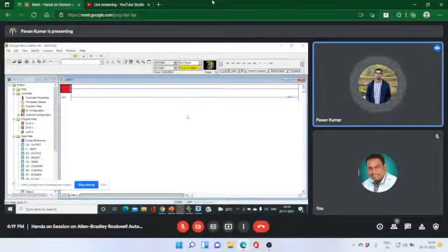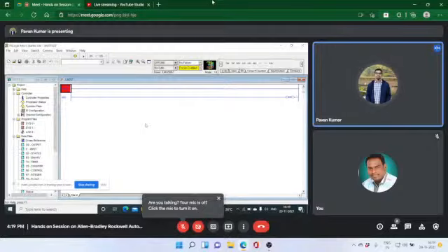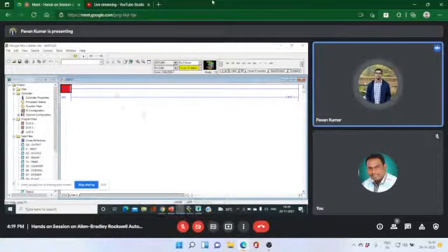In the second case, the RTD shows the liquid temperature is less than the heater temperature, so I should increase the on time of the heater and decrease the off time. In case 3, if the liquid temperature and the heater temperature are equal, then the on and off times should be equal.